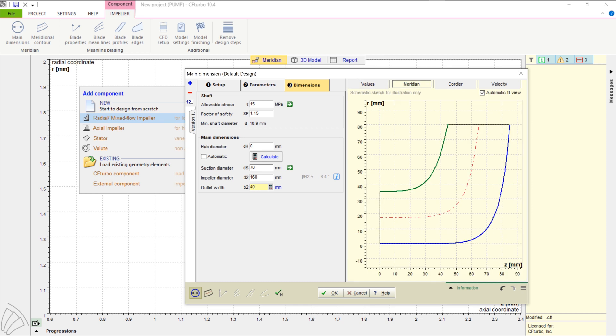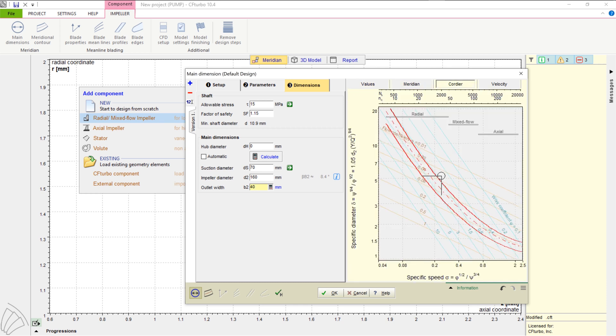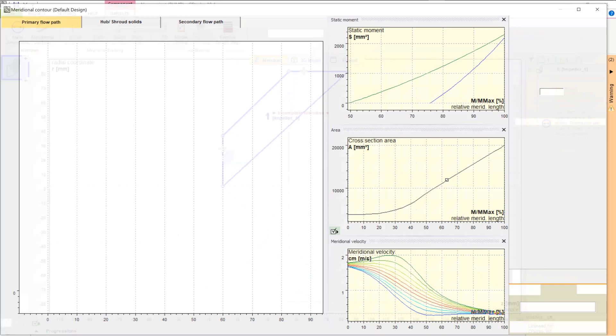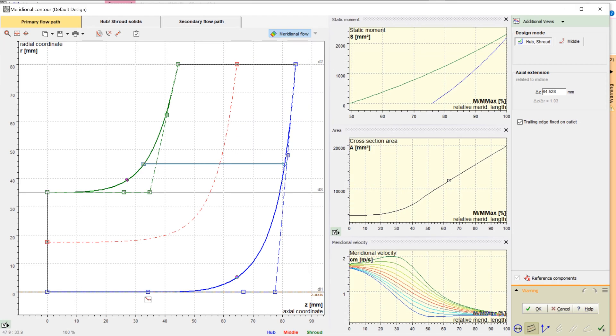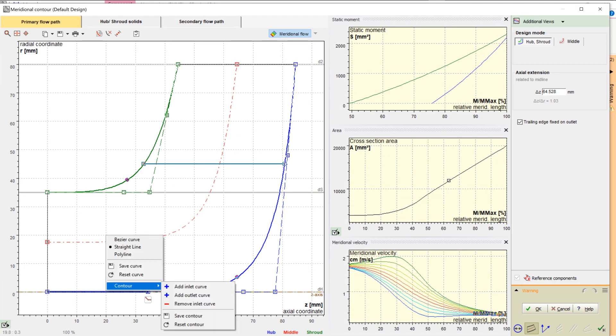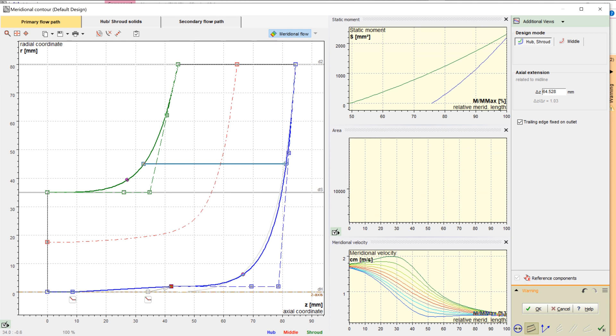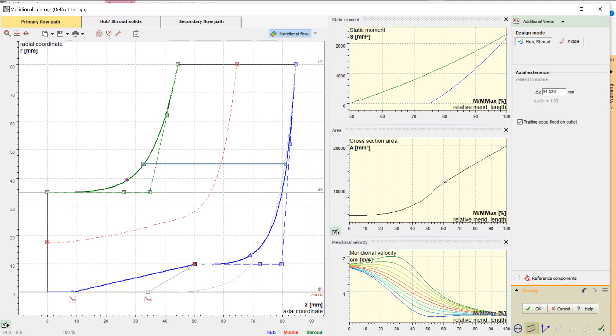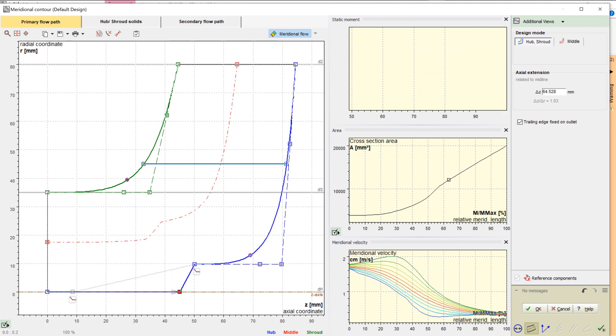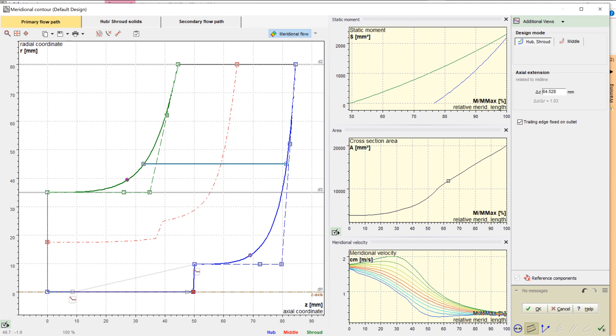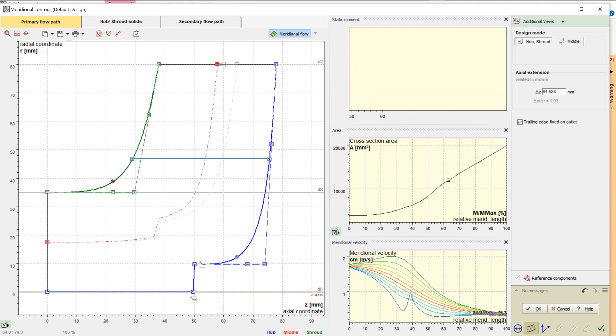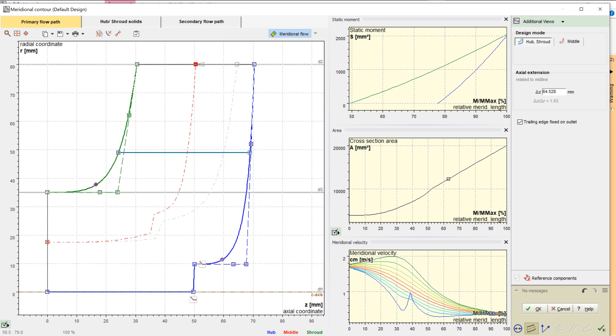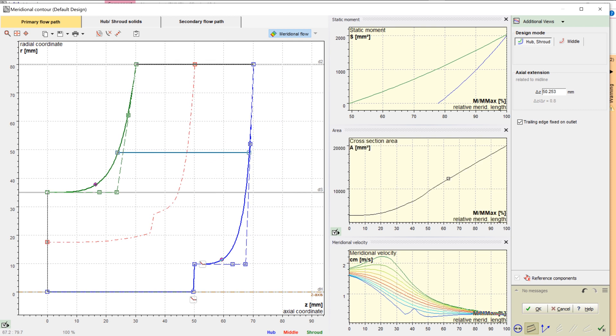On the right side, you see a sketch of the meridional view and the Cordier diagram. The next design step is to create the meridional contour of the impeller. Here, we design the hub and shroud contour of the impeller, modify the axial length, and adjust the position of the leading edge and, if required, the trailing edge. On the right side of the window, you see diagrams of static moment, cross section area, and meridional velocity, which comes from a potential flow calculation.